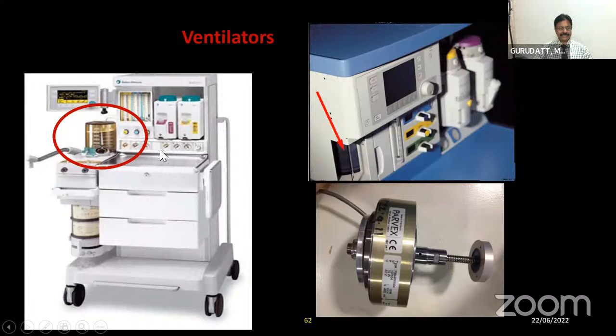One question you'll be asked: suppose the pipeline source is exhausted when you are using a GE machine, so you open the cylinders. What will you be doing? Will you continue with the mechanical ventilator, or will you go for manual ventilation? If you continue with mechanical ventilation, for every breath, whatever tidal volume is going to the patient, that amount of oxygen is also utilized for driving these bellows. So that's the reason, in the case of GE machines, if you are using the backup cylinders, it is better to go for manual ventilation.